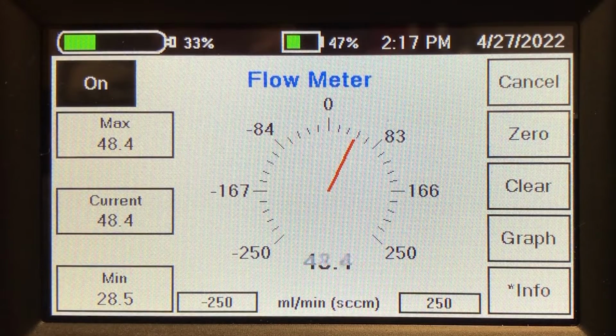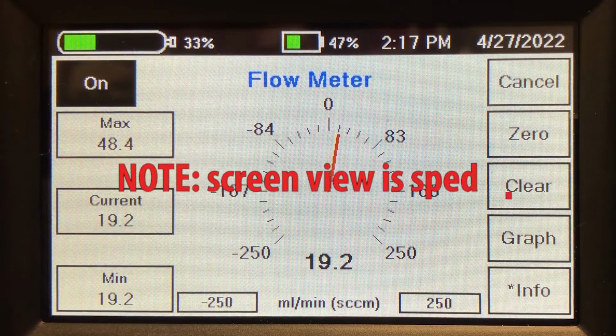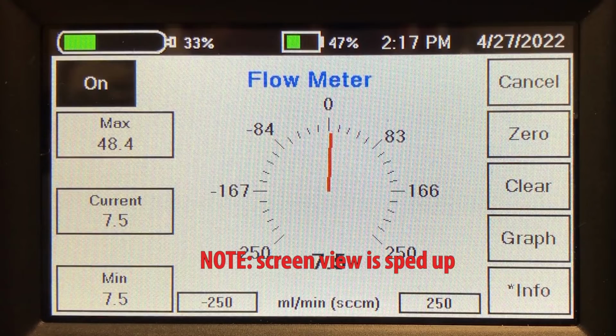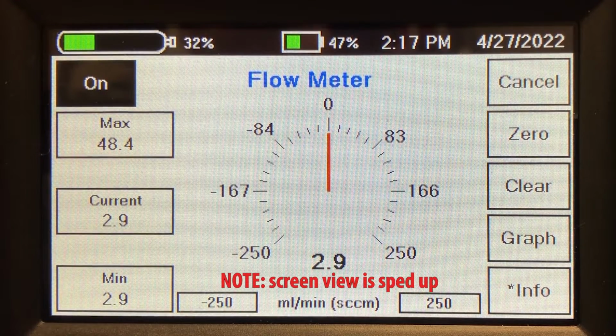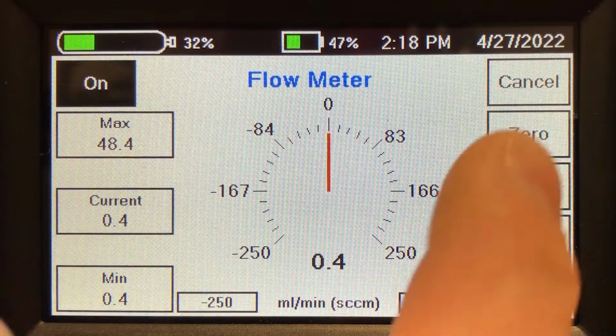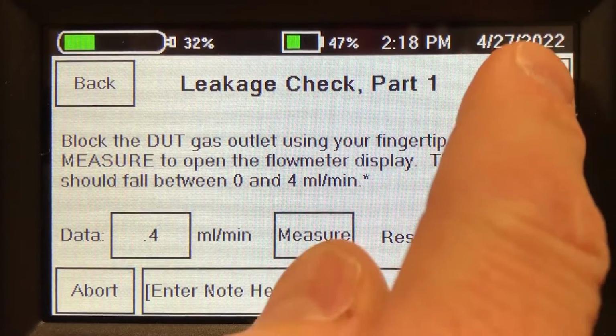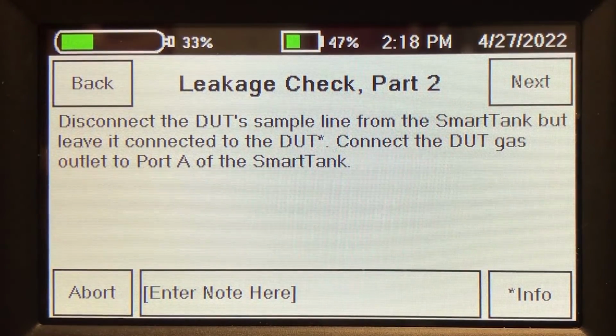Now if I block it off, we'll see that drop down, and that needs to be less than 4 milliliters a minute when it settles in. So this is essentially testing a leak downstream of the pump, and you see that's very close to zero. Okay, so we can exit out of there. It's approximately 0.4 at its lowest. Now we're going to disconnect the sample line.